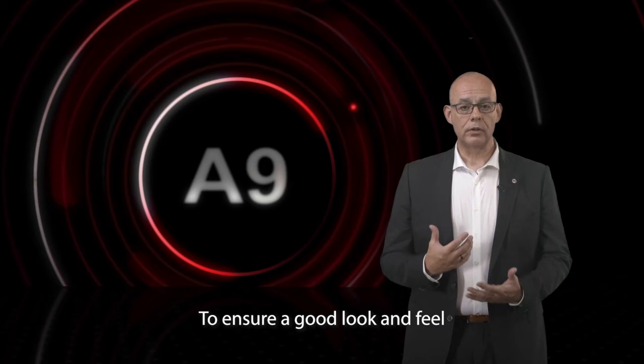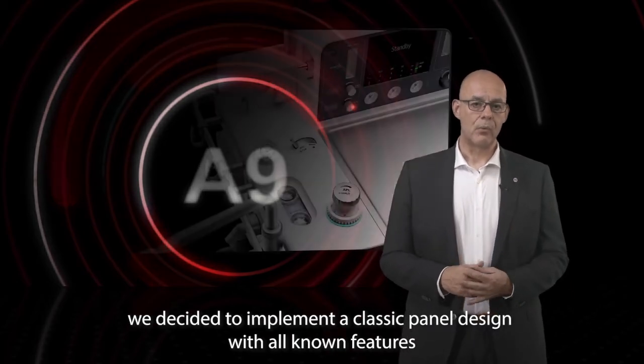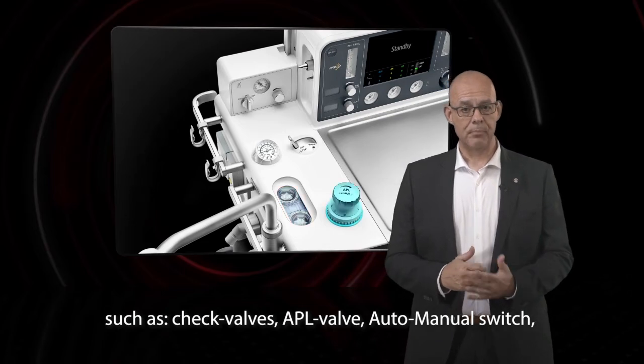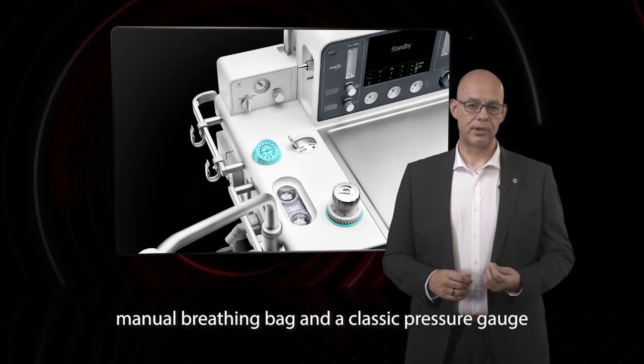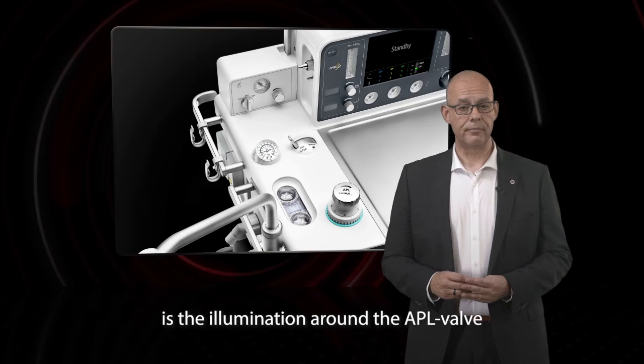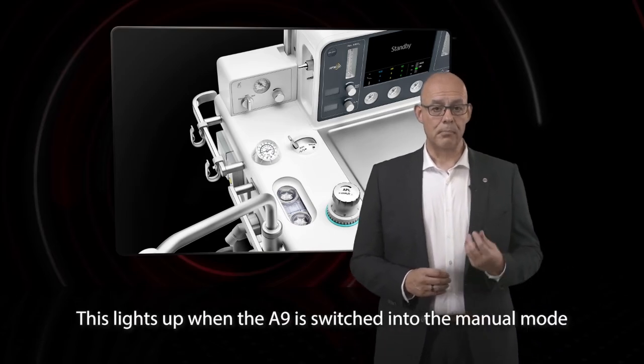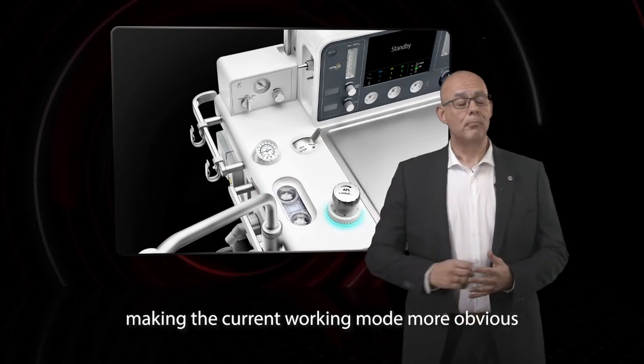To ensure a good look and feel, we decided to implement a classic panel design with all known features such as check-valves, the APL valve, auto-manual switch, the manual breathing bag, and the classic pressure gauge. A nice feature that draws attention is illumination around the APL valve, which lights up when the A9 is switched into manual mode, making the current working mode more obvious.